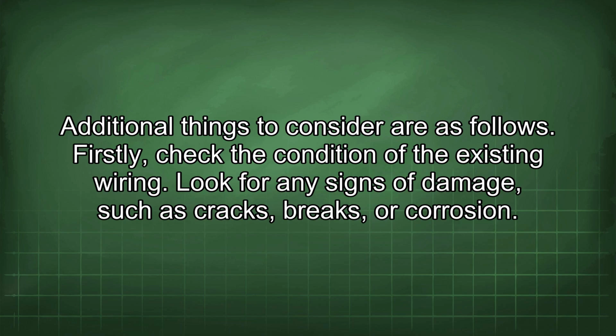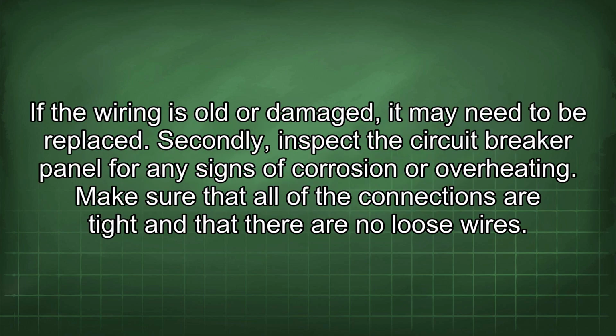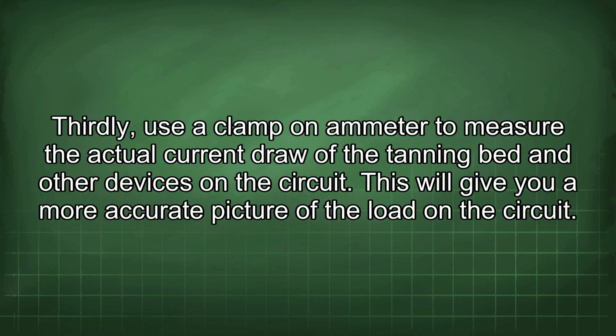Firstly, check the condition of the existing wiring. Look for any signs of damage, such as cracks, breaks, or corrosion. If the wiring is old or damaged, it may need to be replaced. Secondly, inspect the circuit breaker panel for any signs of corrosion or overheating. Make sure that all of the connections are tight and that there are no loose wires. Thirdly, use a clamp-on ammeter to measure the actual current draw of the tanning bed and other devices on the circuit. This will give you a more accurate picture of the loads on the circuit.